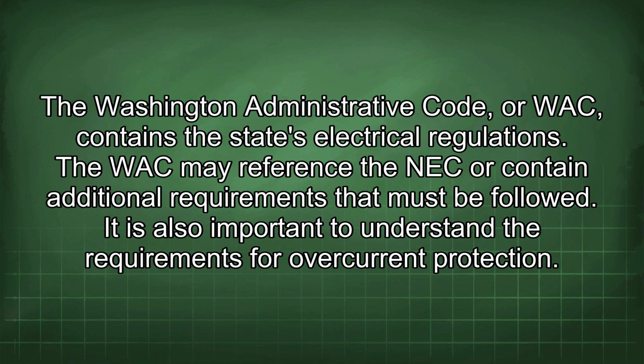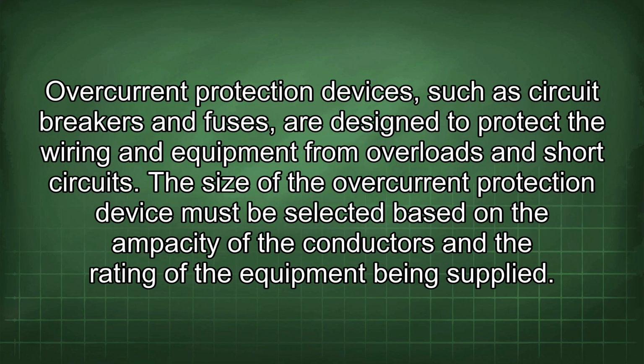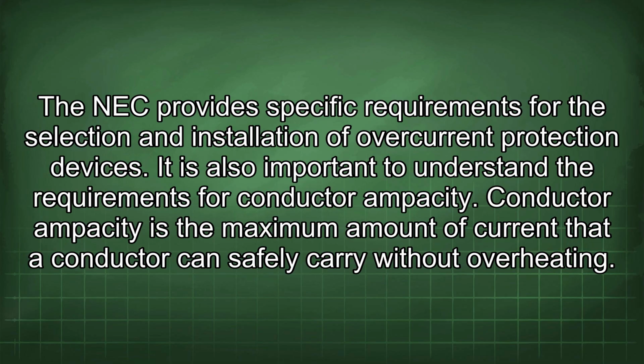It is also important to understand the requirements for overcurrent protection. Overcurrent protection devices, such as circuit breakers and fuses, are designed to protect the wiring and equipment from overloads and short circuits. The size of the overcurrent protection device must be selected based on the ampacity of the conductors and the rating of the equipment being supplied. The NEC provides specific requirements for the selection and installation of overcurrent protection devices.